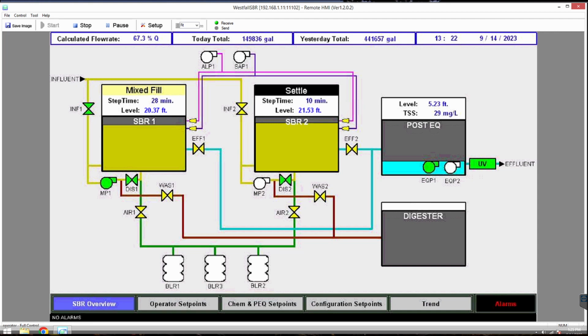In instances like that, if the control system knows what the DO level is, we put set points in there to say, once your DO gets above 3.5 or 4, get out of aeration. There's no reason to continue, because it's just rainwater, and it's probably got high DO coming in the first place. So you can speed your cycles up way more and get the hydraulic load through there and not sacrifice any of your treatment. The whole system runs a lot better.